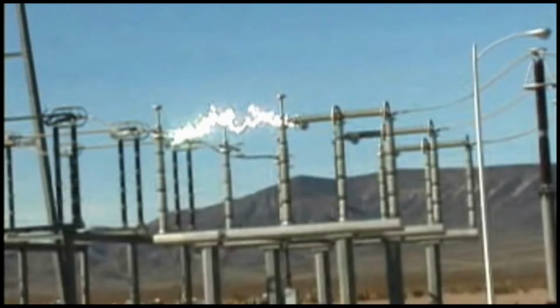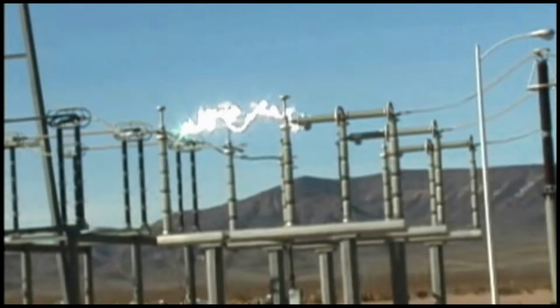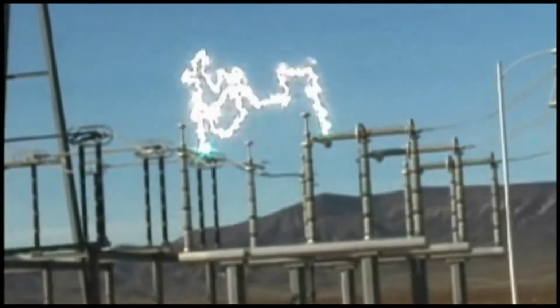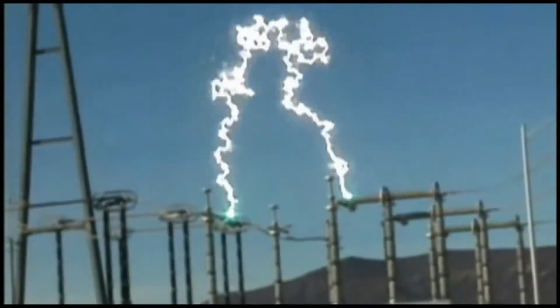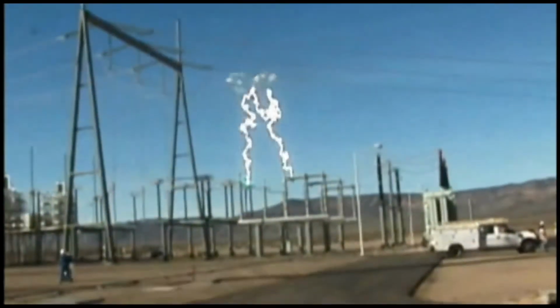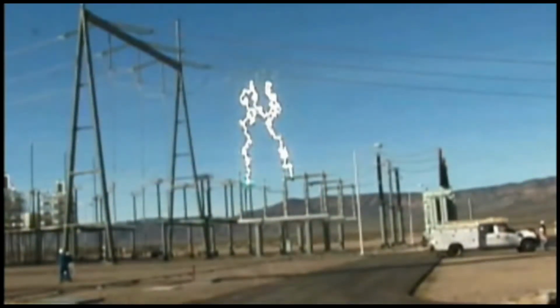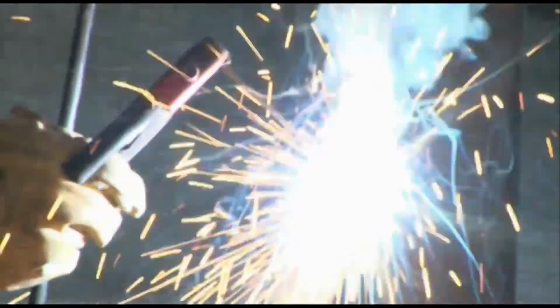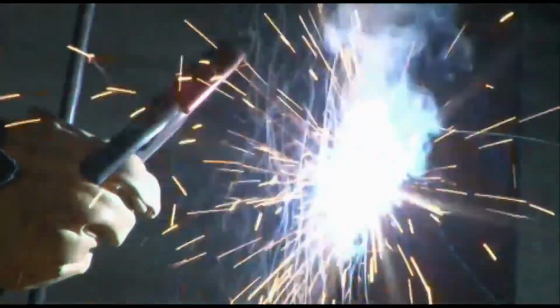You can see that an electrical arc can be sustained over a gap of many feet through nothing but air. There is a specific distance where electricity will jump across an air gap between two conductors, like the spark in a spark plug or an arc welder. This is called the arc over distance. The distance the arc will jump depends upon the voltage. The more voltage available, the further it will jump.